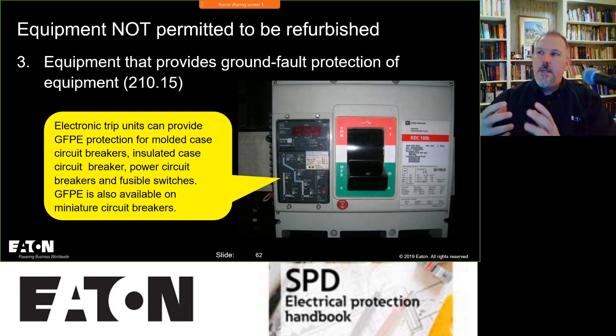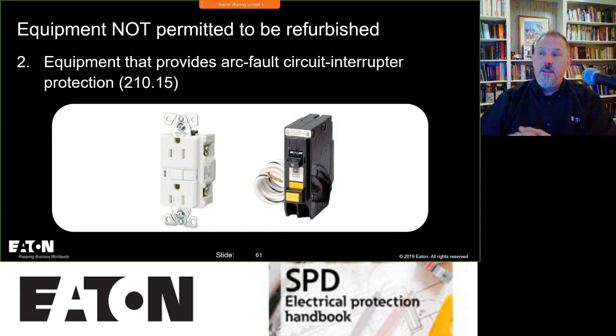This might be a question of whether this is the right place for some of these requirements. For example, in branch circuit 210 we have a molded case circuit breaker that's a GFCI, and we have a receptacle that's a GFCI. There are requirements in Article 240, which talks about overcurrent protection, and in 406, which talks about wiring devices, that already say you can't recondition or refurbish receptacles or molded case circuit breakers. So there's probably no need to have it in 210.15.